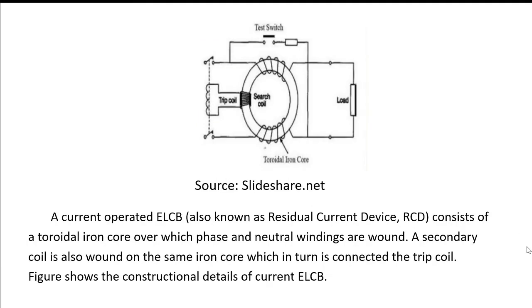The other ELCB is the current operated ELCB. Here is the circuit diagram of current ELCB. A current operated ELCB, which is also known as residual current device RCD, consists of a toroidal iron core over which phase and neutral windings are wound. A secondary coil is also wound on the same iron core, which in turn is connected to the trip coil as shown in the circuit diagram. Here, this figure shows the constructional details of current ELCB.